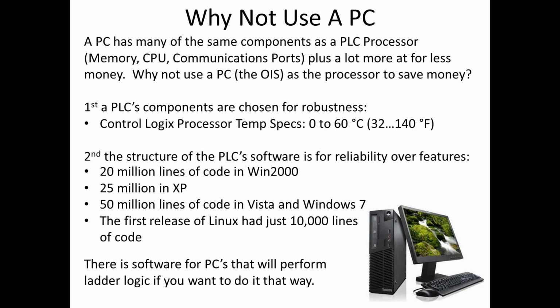So if there isn't any difference between a PC that you buy at the hardware store and a PLC, one of the differences is the cost. You can go to your local electronics retail store and buy a PC that's on sale for $600, whereas a full-scale PLC may run up to $30,000. I don't know the exact numbers there. I do know that PLCs can be incredibly expensive, especially when you're comparing them against a laptop. So why don't we just use a PC for the processor just to save money?